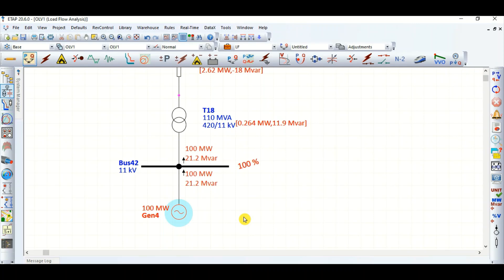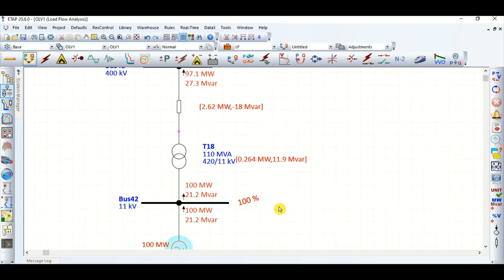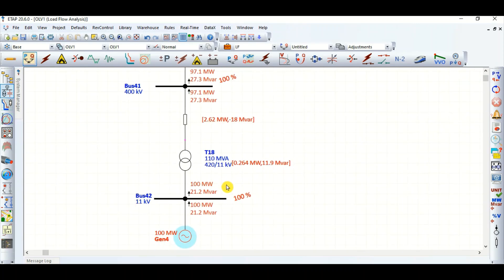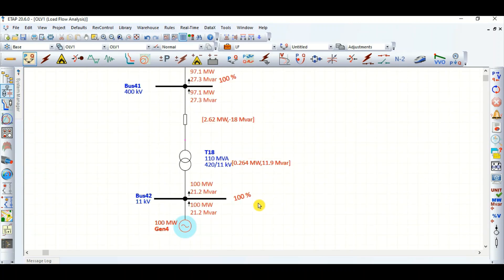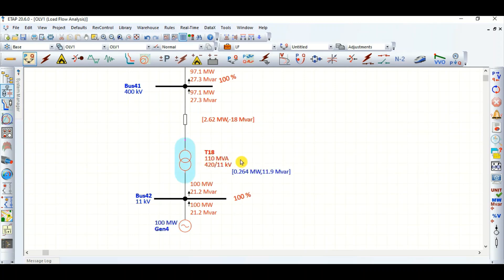This is the basic concept of how we can extract some reactive power that is required to be supplied towards the grid. In almost all real projects you will see the transformer primary side is 420 kV while the bus voltage is 400 kV.